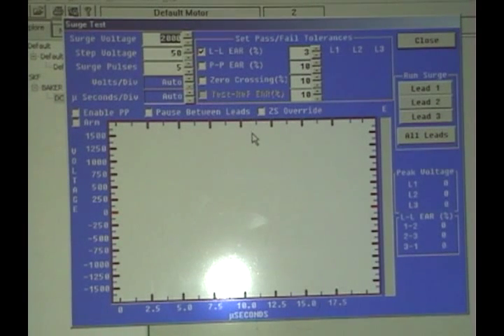This is where we want to surge test utilizing the span testing. First thing we'll do is set the voltage that we want to obtain, which is 2,000 volts. The step voltage and the pulses are really not of any interest for doing span testing.